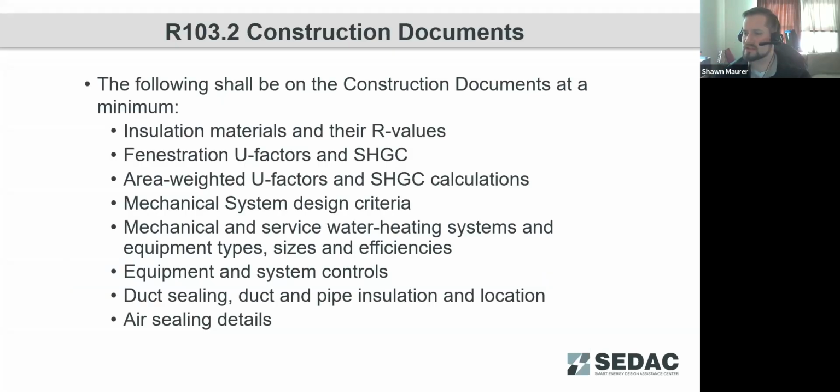Moving into the plan review, and what kind of initial documentation you need to have prepared in order to draft that plan review process. You'll need to have in your construction documents at a minimum, either on the plan drawings or in your specification documents, insulation materials and their listed R values, fenestration U factors and solar heat gain coefficients. If you're following an area weighted U factor and solar heat gain coefficient compliance option, then you'll need to show those calculations. Same if you're doing insulation through the UA trade-off method, you would need to show that UA trade-off calculation and that it's in compliance.